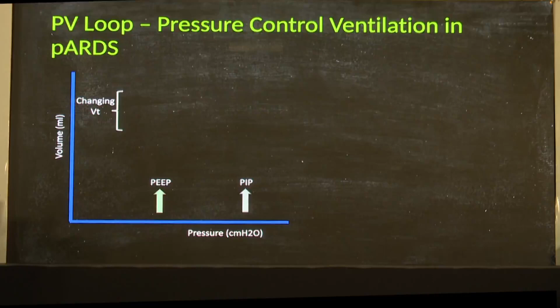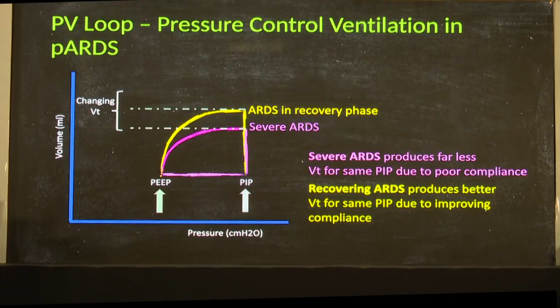The pressure is achieved within a few milliseconds and it remains the same. So you just need to see only the volume achievement. So if there is a poor compliance, you will have a small volume, and as the compliance is improving in pressure control mode in PV loop, you will only see the improvement in the volume achieved. This is the pressure overdistension beak, as we know, in pressure volume loop, and this is the air leak we see, and this is the flow starvation. So these are the things.